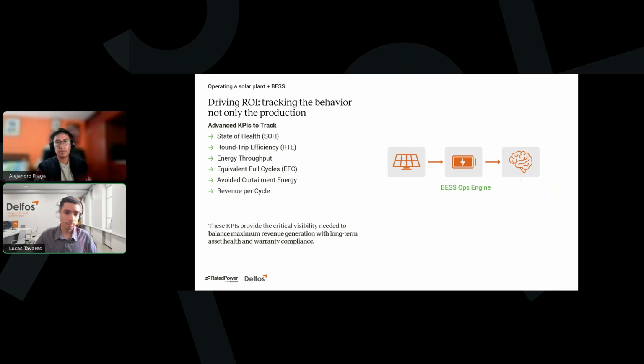We also highlight equivalent full cycles, which normalizes all partial charge and discharge cycles into full cycle equivalents. For example, charging from 50% to 100% and then discharging back to 50% equals 0.5 equivalent full cycles. This metric provides a more accurate measure of battery usage and aging than raw cycle counts, especially for real-world operations where partial cycles are common.